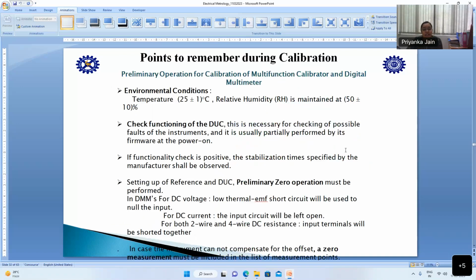Next are some of the points which we need to remember while doing the calibration. So, preliminary operation of calibration of the multifunction calibrator and DMM. Most of the private laboratories and regional laboratories use an MFC and DMM to calibrate their customers' DUCs, whatever they are. We maintain a temperature of 25 plus or minus 1 degree Celsius. Here the temperature plays a major role. If the temperature is not within this range, then the calibration has no meaning at all, because all the values are defined for a particular temperature and humidity. So these values play an important role while we are calibrating. We maintain the temperature at 25 plus or minus 1 degree Celsius and the relative humidity at 50 plus or minus 10 percent.